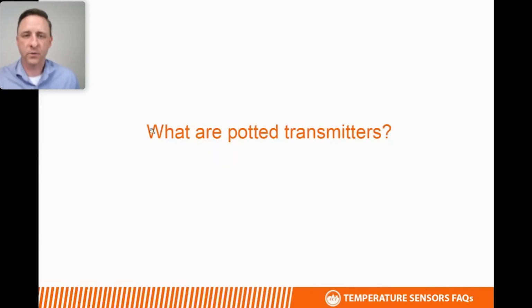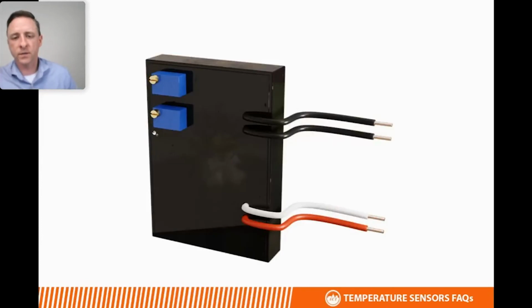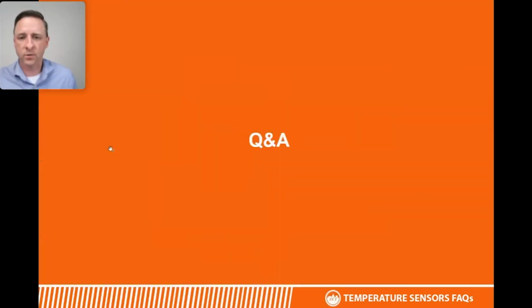What are potted transmitters? That's something we've had for the last few years now, and that's essentially a transmitter board that is completely encapsulated in epoxy, in which the leads are tied into the terminal blocks, and there are just flying lead wires coming out. That is a great solution for very high humidity or other rugged applications that require a very rugged and durable transmitter and electronics. Sometimes these are referred to as ruggedized, or you'll see them with an R in the part number, or they're sometimes called potted transmitters.